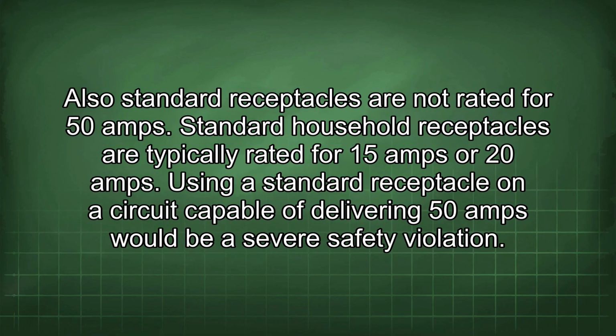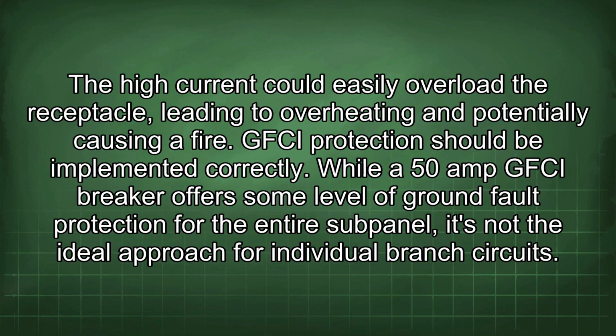Also, standard receptacles are not rated for 50 amps. Standard household receptacles are typically rated for 15 amps or 20 amps. Using a standard receptacle on a circuit capable of delivering 50 amps would be a severe safety violation. The high current could easily overload the receptacle, leading to overheating and potentially causing a fire.